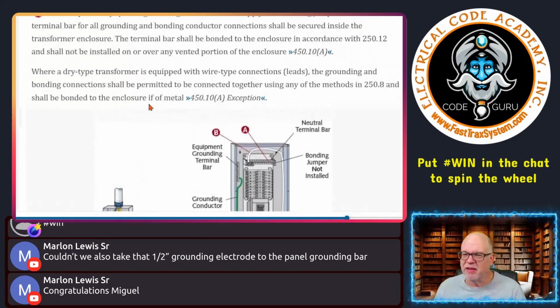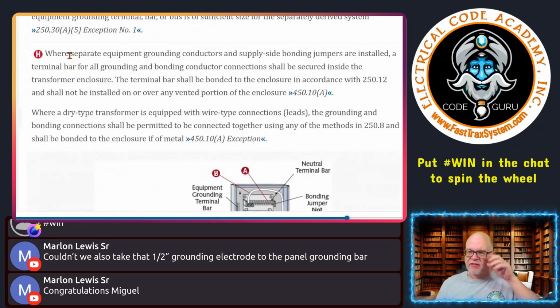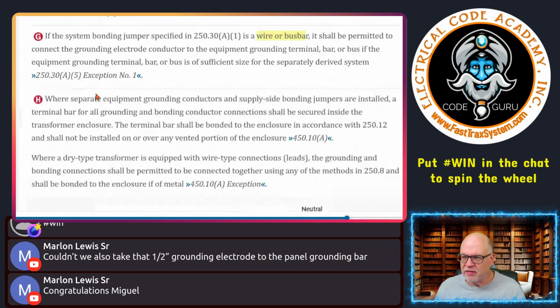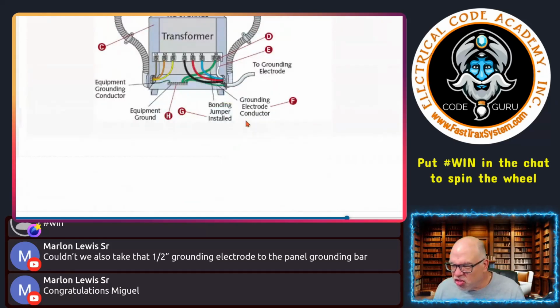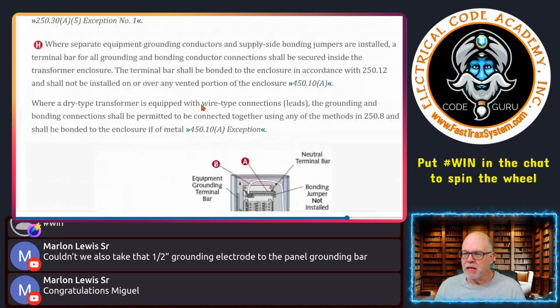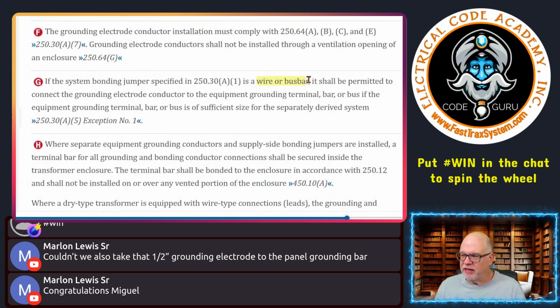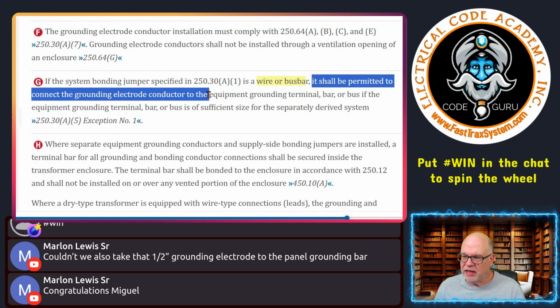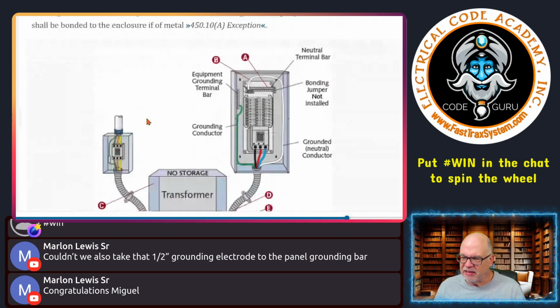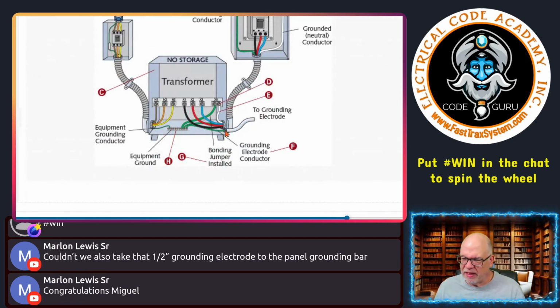It's just talking about the bus here. So where the separately, what's this say, let's see here. Oh, we're back in G still. G, we're still talking about the use of this jumper. So it is permitted to connect the grounding electrode conductor to the equipment grounding terminal bar. So I could have taken, that's why I can take it here. So that's why this right here, if you see this, this is why this is right here.